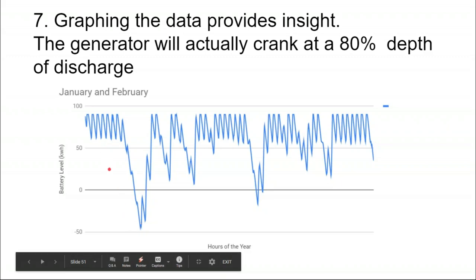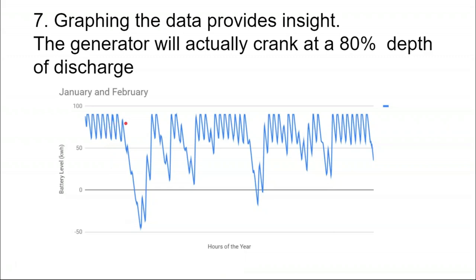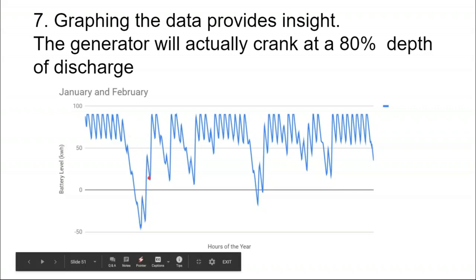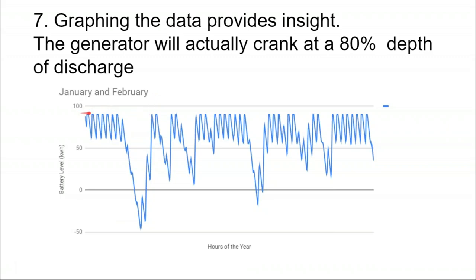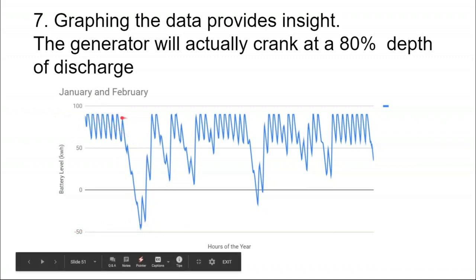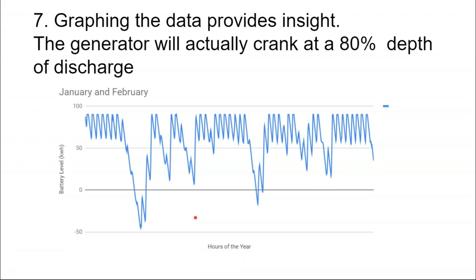If we had an infinitely large battery bank, we know that at the end of the month we're catching back up because our solar array is sized enough. It only takes a few sunny days to get us all the way back up to the top. But if this is reflective of 90 right here, and this is reflective of negative 50, what we're saying is without a generator our battery bank would need to be 90 plus 50, so 140 kilowatt hours, to not need a generator. And that would be right on the nose. Generally, you don't size a critical function like electricity to be right on the nose, unless you have millions of customers buying into one platform.